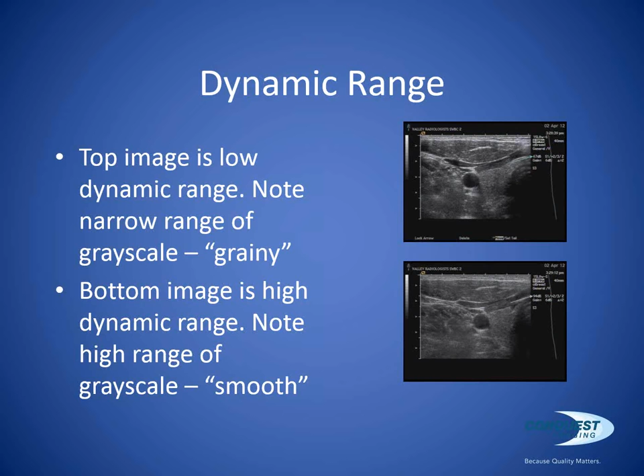So you can see from these two images here, what you're looking at is my thyroid. For soft tissue, like a liver, a thyroid, breast, things like that, a testicle, you would want to use a higher dynamic range. You want to see all those wonderful shades of gray. You can see that the top image is very grainy, and that's a very typical sonographer term. My image is grainy. The bottom image is very smooth. We have a lot more information. We're getting a lot more shades of gray. So with a thyroid, a high dynamic range is good.